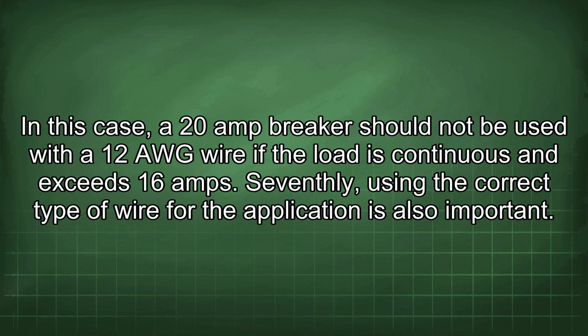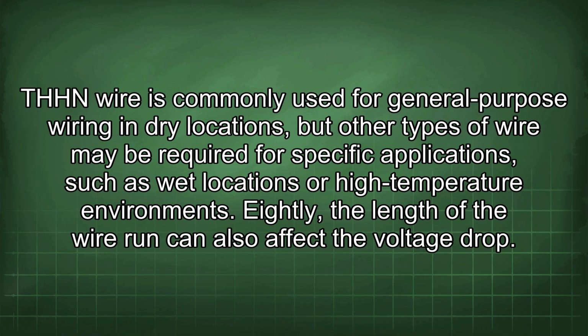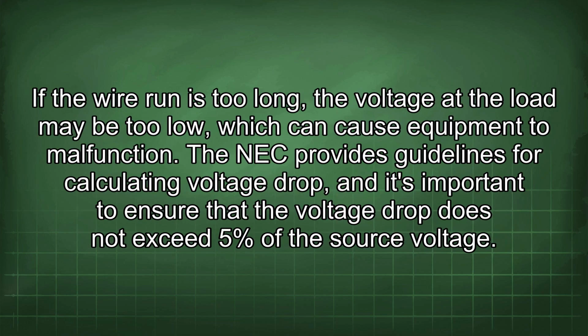Seventhly, using the correct type of wire for the application is also important. THHN wire is commonly used for general-purpose wiring in dry locations, but other types of wire may be required for specific applications, such as wet locations or high-temperature environments. Eighthly, the length of the wire run can also affect the voltage drop. If the wire run is too long, the voltage at the load may be too low, which can cause equipment to malfunction. The NEC provides guidelines for calculating voltage drop, and it's important to ensure that the voltage drop does not exceed 5% of the source voltage.